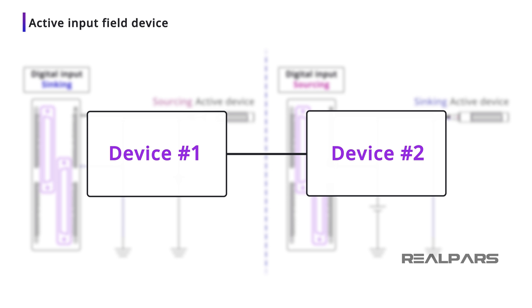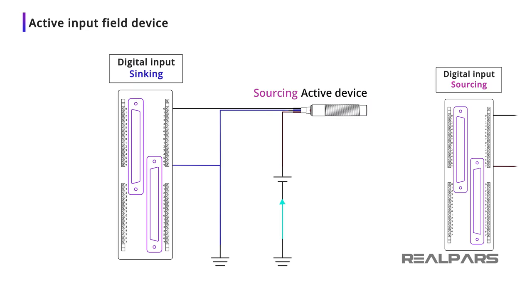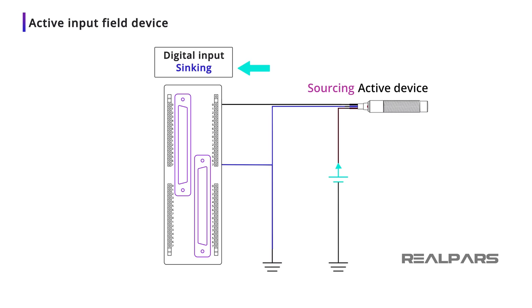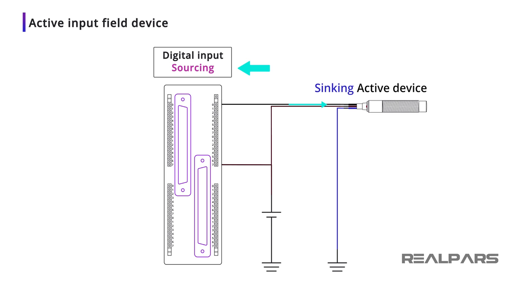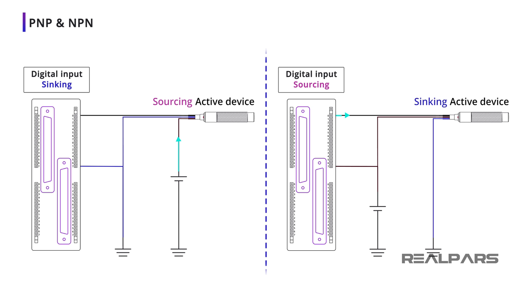Earlier we said that when there are two devices with current flowing between them, one device will be sourcing and one will be sinking. If the input device is a sourcing type, the PLC input module must be a sinking type. If the input device is a sinking type, the PLC input module must be a sourcing type. Adding to the confusion, some vendors refer to sinking and sourcing input devices as NPN and PNP. You can learn more about NPN and PNP in our other videos.